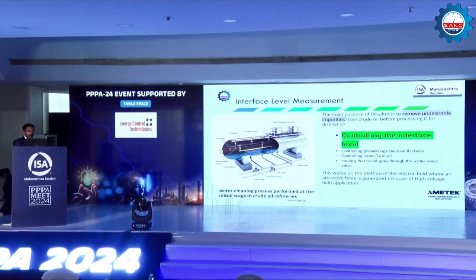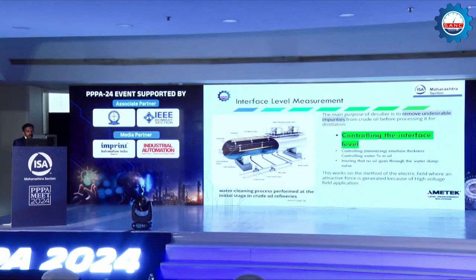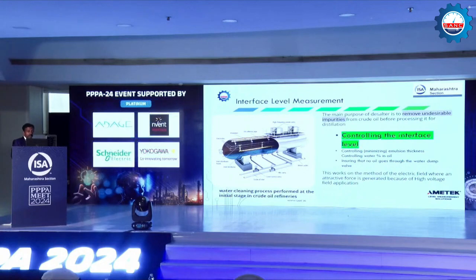What we are doing here is this: the level transmitters that we put inside the desalter for interface level actually measure only the water level. It does not measure the oil. That is how we calibrate it. How are we calibrating it?